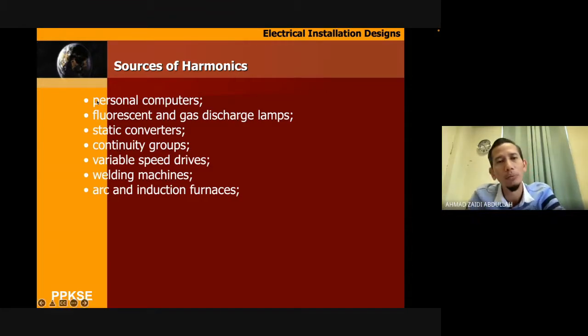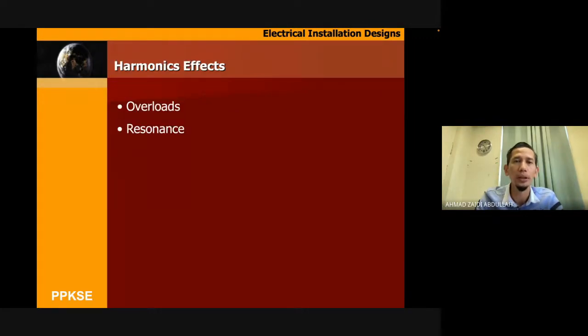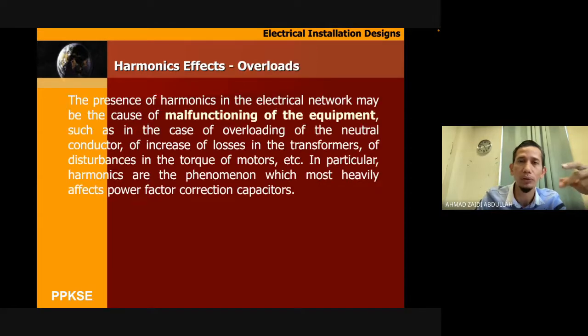And then source of harmonic also comes from static converter, continuity group, variable speed drive, welding machine, arc and induction furnace, these hot things. Okay, so that's some of the sources of the harmonic. And then the effect from the harmonic normally divides into two. One is overload and number two is resonance.